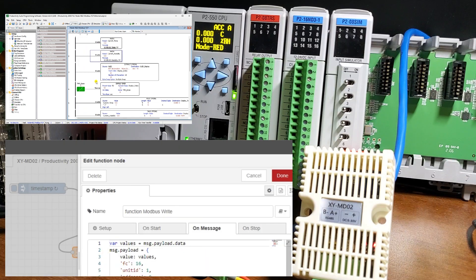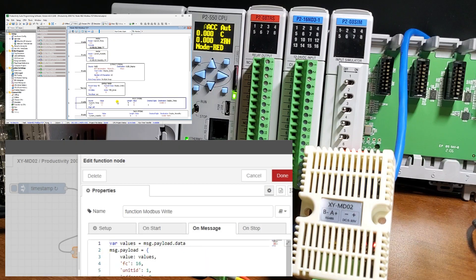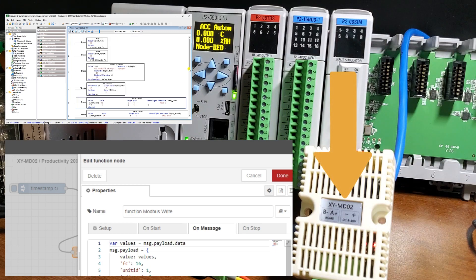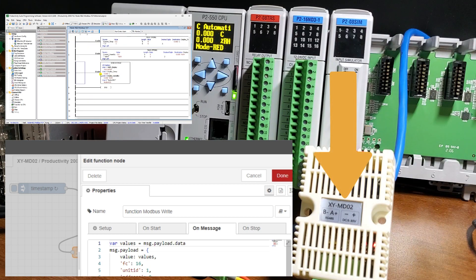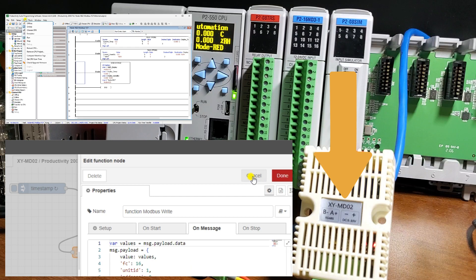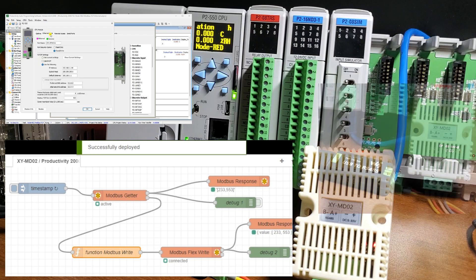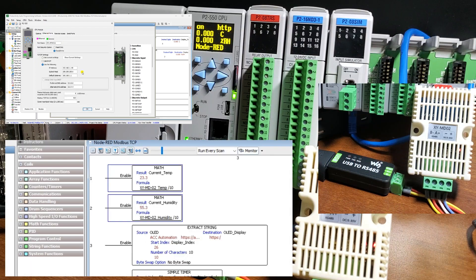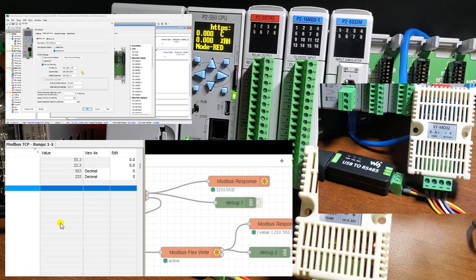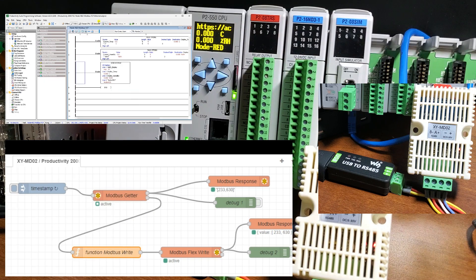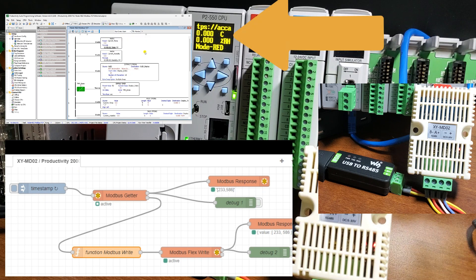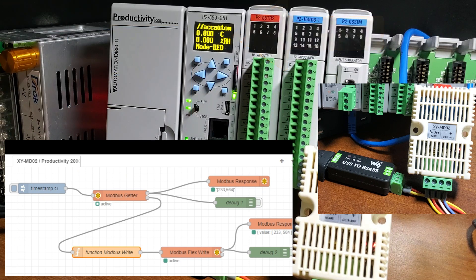Node-RED will be used to create a single Modbus flow. We will communicate to our XY-MD02 temperature and humidity sensor using Modbus RTU on a serial RS-485 network. The present values of the sensor will be read and then written to the Productivity 2000 PLC using a Modbus Ethernet TCP network. These temperature and humidity readings will then be displayed on our P2000 CPU.